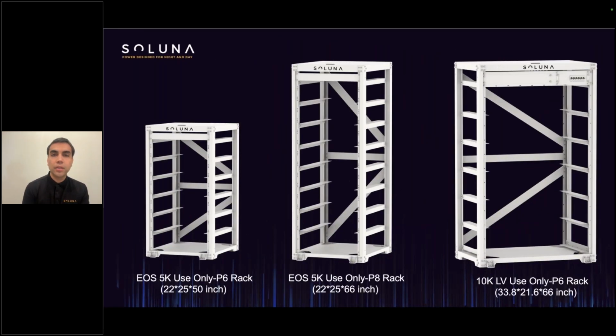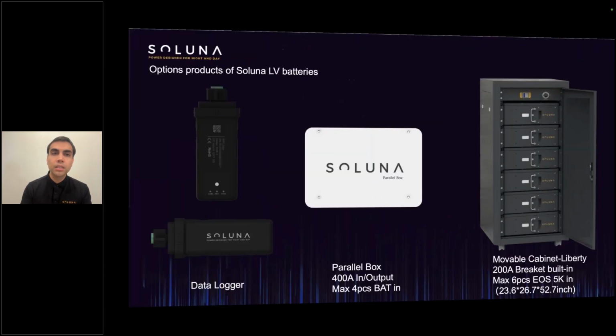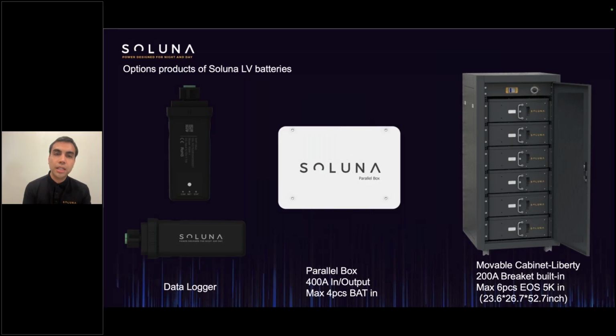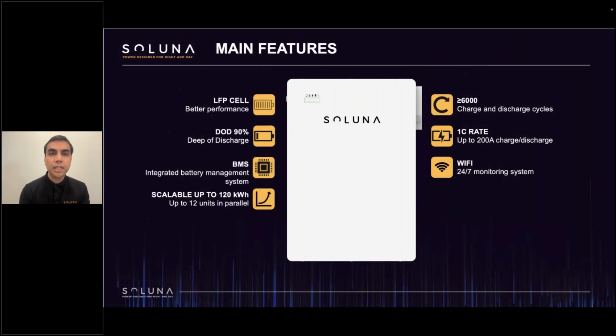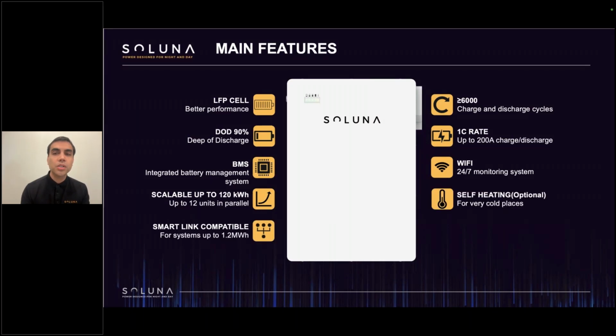These are the racks that we manufacture for the 10K. You have 6 racks with 6 slots. You have the on and off switch on the top, which allows you to turn them all on or all off in one location. You have the optional products, which are the data logger, the parallel box, and also the movable cabinet that is IP65 for places with higher humidity or salt in the air. It's scalable, and it also has a self-heating option.